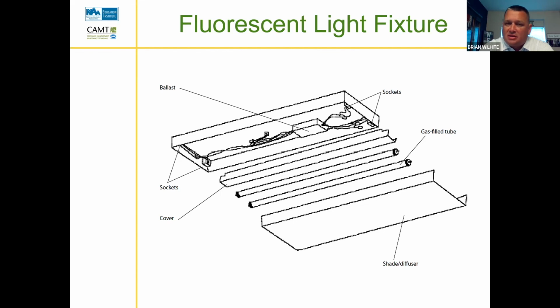So a couple things to notice. If you get a chance, then you're going to replace one of these. Obviously now things are changing. If you can replace them with LEDs, that's the way to go. If you have to change those though, and you have T12s, go to T8s. Shorten those wires up so they're not so bunched up that you get them caught underneath the cover. Those diffusers, they get brittle and cracked. So if you're going to take those off, go real easy with them because more than likely you can break those. Any questions up to now?